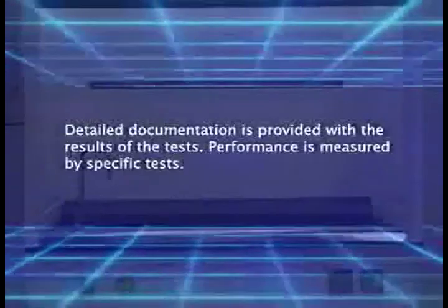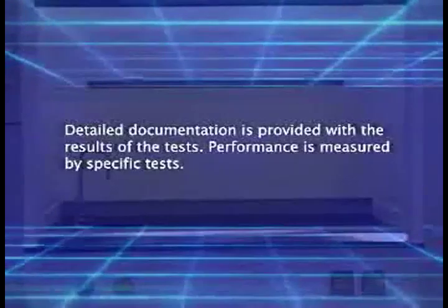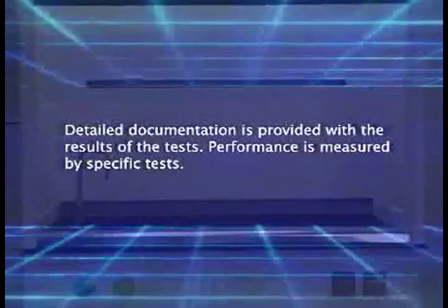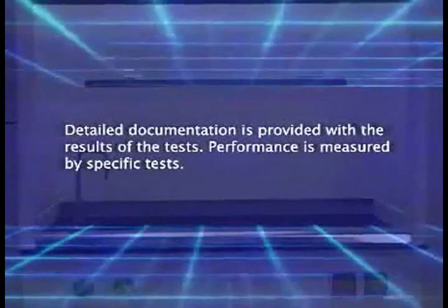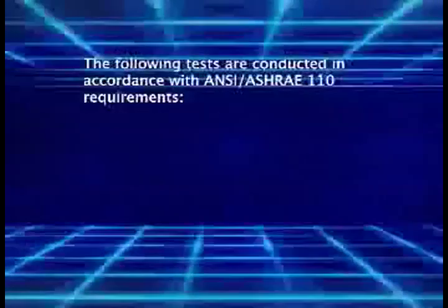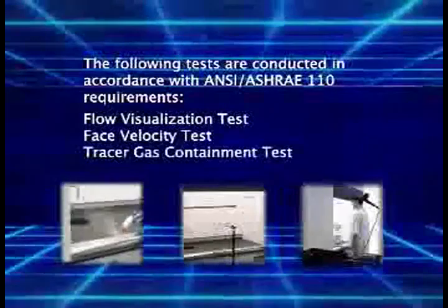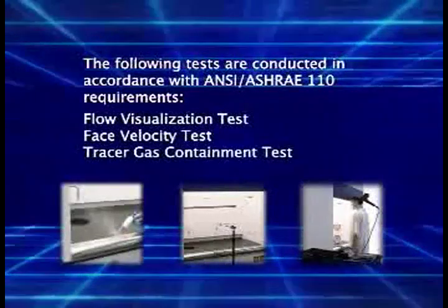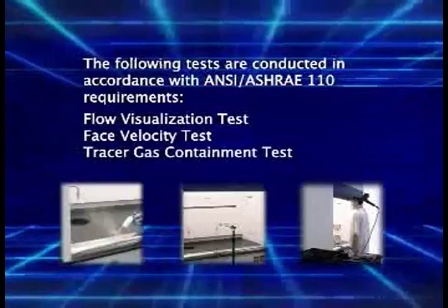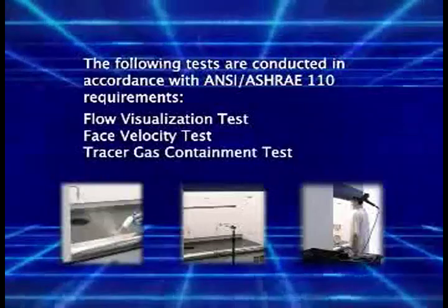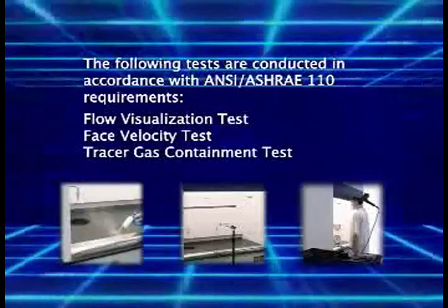Detailed documentation is provided with the results of each test in accordance with the standard's requirements. We undertake flow visualization, face velocity, and tracer gas containment tests.